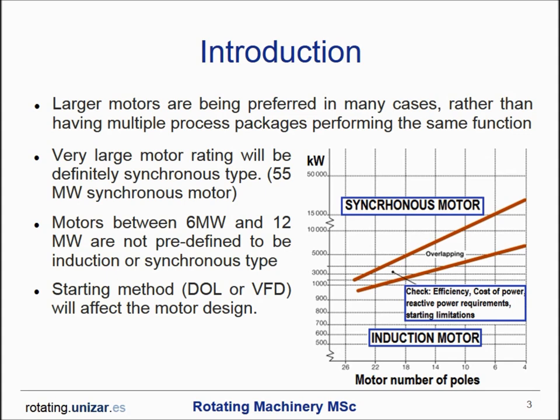Different starting methods need to be evaluated to satisfy the electrical network requirements, load torque curves, and inertia of the load. These different starting systems also have an effect on the motor design, due to the high starting current in the case of direct line starting, or due to the presence of harmonics when variable speed drives are used.